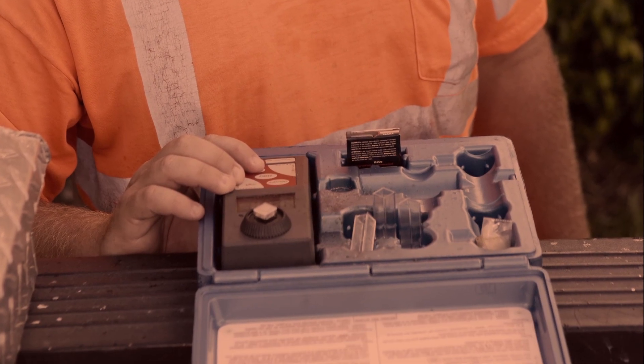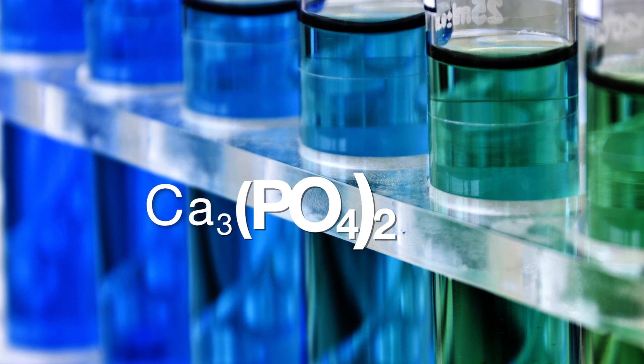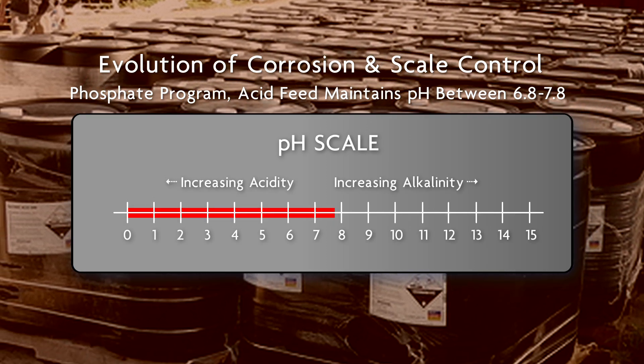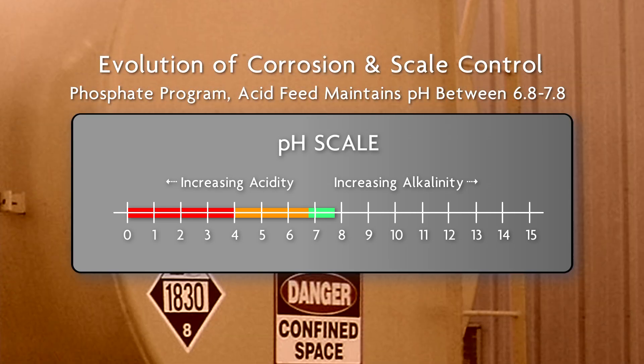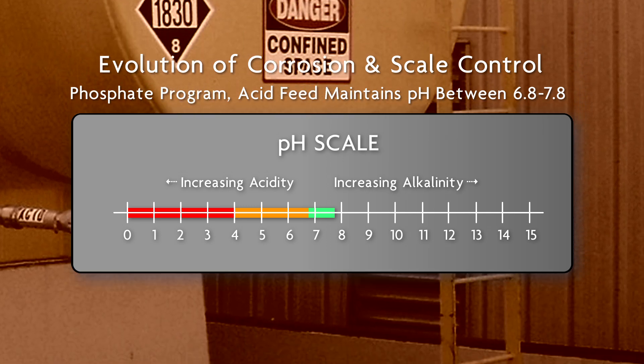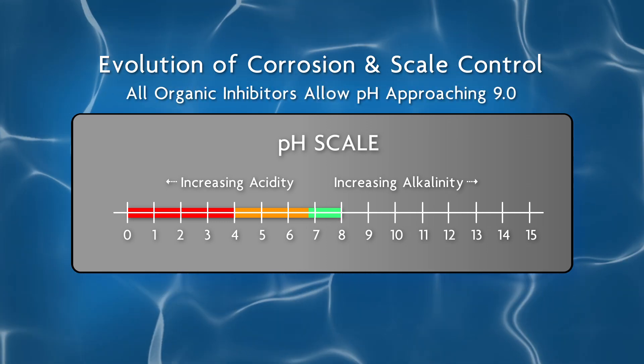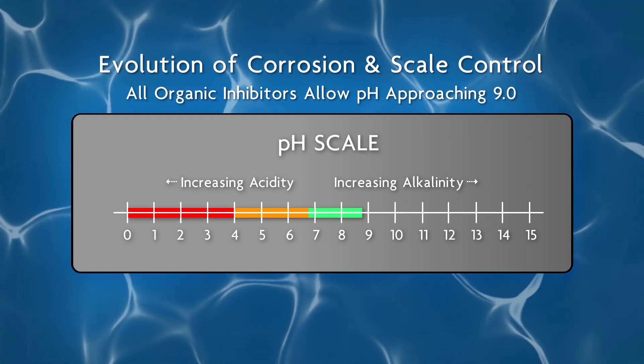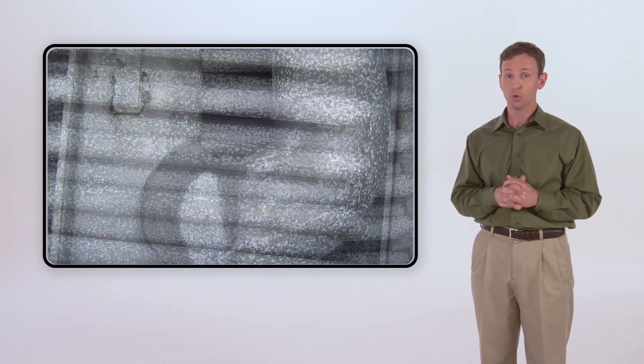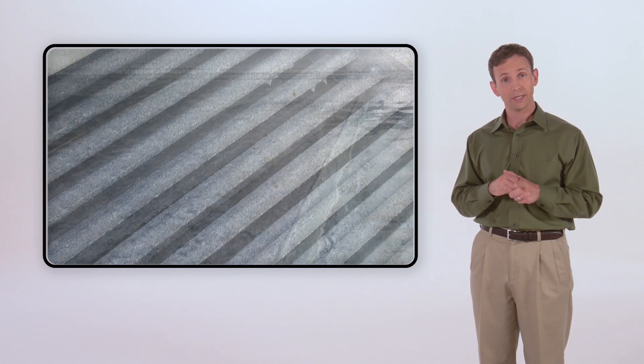In response, the water treatment industry initially transitioned to stabilized phosphate programs. To avoid calcium phosphate deposition inside systems, acid was typically fed to maintain pH between 6.8 and 7.8. Customers' safety concerns created a desire to eliminate the ongoing feed of sulfuric acid to control evaporative cooling water's pH. This led to further advances in corrosion and scale control, which resulted in all-organic inhibitors that could operate with water pHs approaching 9.0. As the organic chemistries capable of operating at higher pH ranges grew in popularity, reports of premature corrosion of the protective zinc layer, known as white rust, became more prevalent.